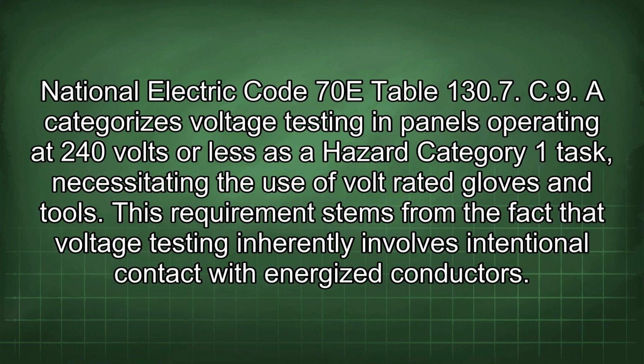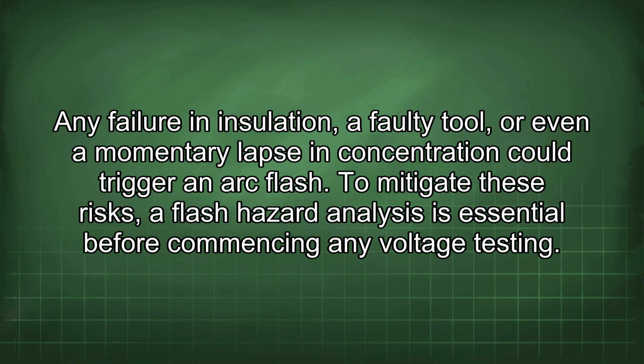National Electric Code 70E Table 130.7 C9 A categorizes voltage testing in panels operating at 240 volts or less as a hazard category 1 task, necessitating the use of volt-rated gloves and tools. This requirement stems from the fact that voltage testing inherently involves intentional contact with energized conductors. Any failure in insulation, a faulty tool, or even a momentary lapse in concentration could trigger an arc flash. To mitigate these risks, a flash hazard analysis is essential before commencing any voltage testing.